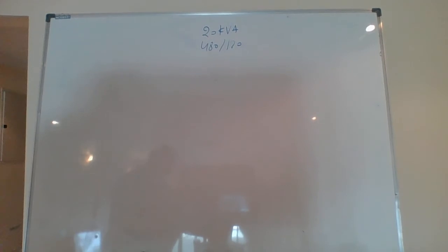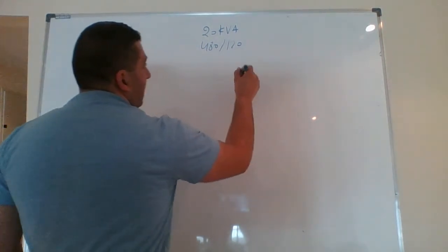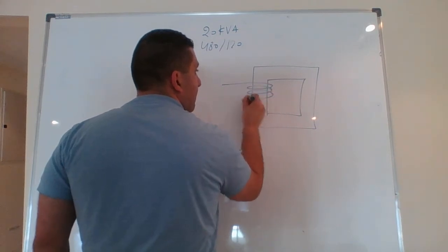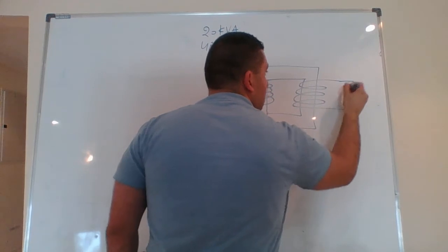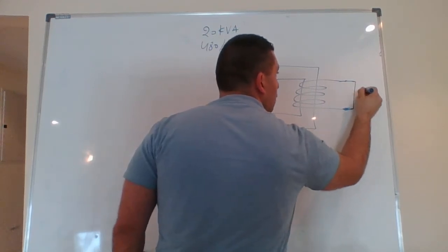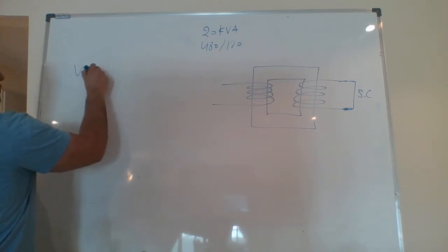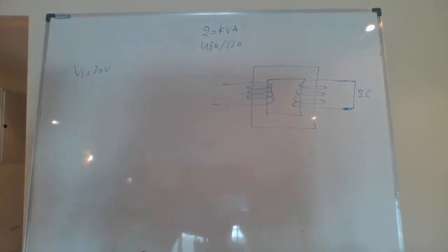During the short circuit test, rated current is applied to the 480-volt winding with the 120-volt winding shorted. A short circuit is applied on the 120-volt winding, and the readings obtained are: V1 equals 30 volts and P1 equals 300 watts.